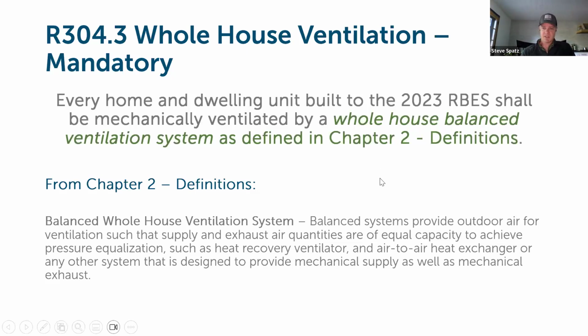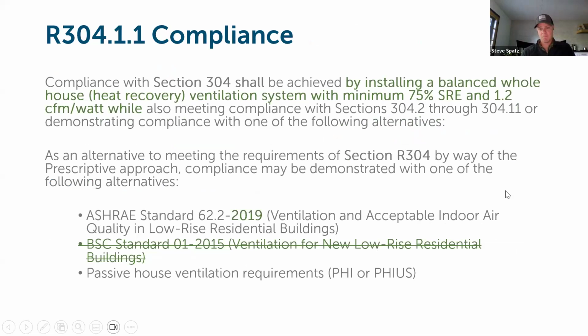Quite honestly, this is something that's catching up to what we're already seeing as a need for new buildings. The air tightness of the building envelope and just the materials involved in the assemblies, as I've been talking about here, have really already steered us in the direction of needing a good balanced mechanical ventilation system rather than just exhaust only. So this is something that has been around for a while. There are many systems installed, and what hopefully we can look at here are just the fundamentals about how to get a good system installed, beyond just the piece of equipment that does the heat recovery and the ventilation.